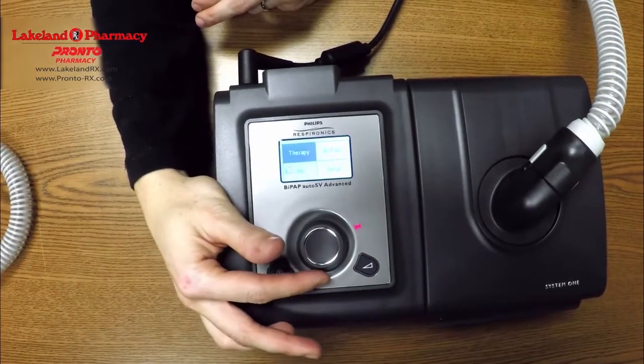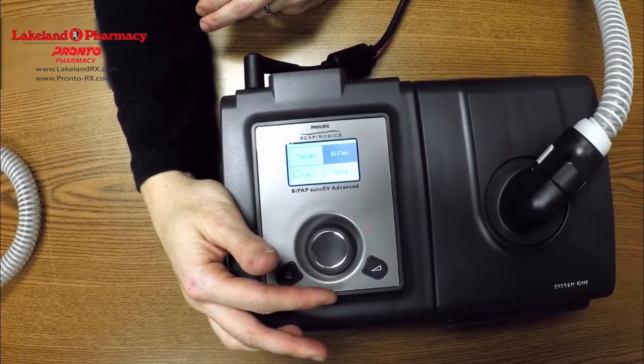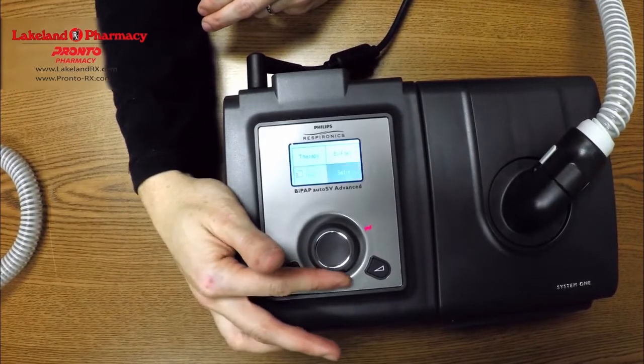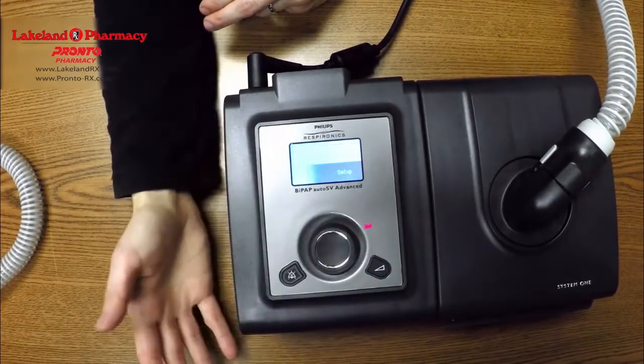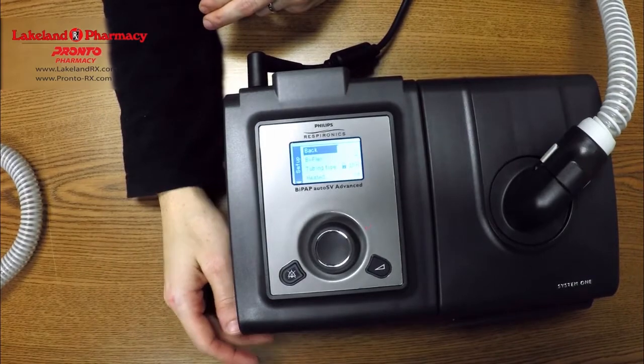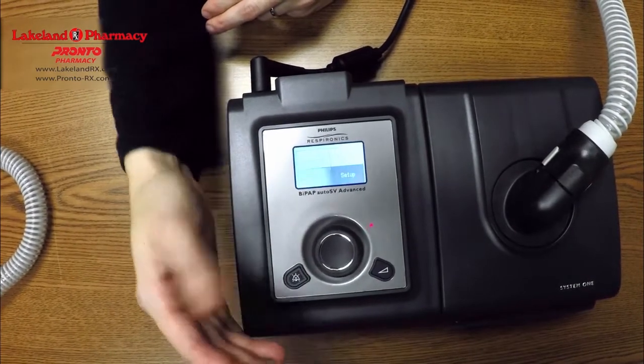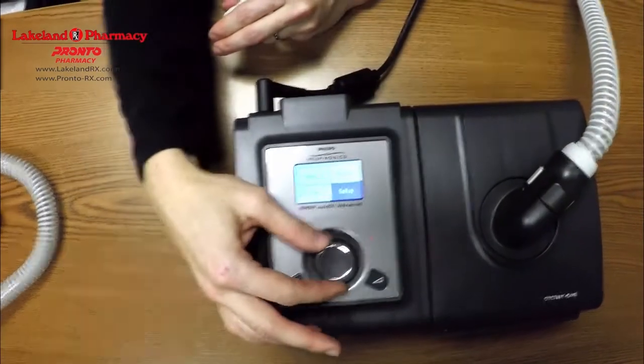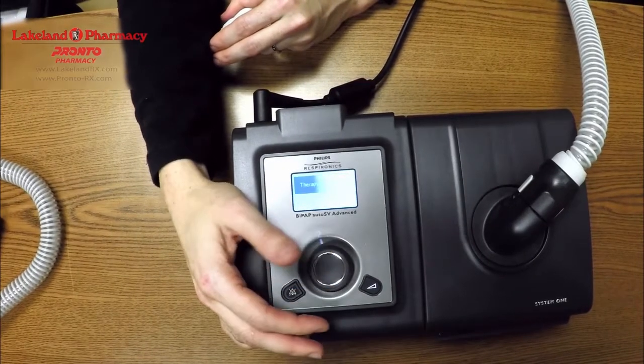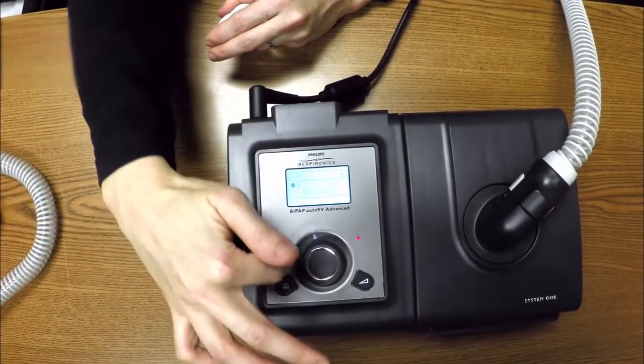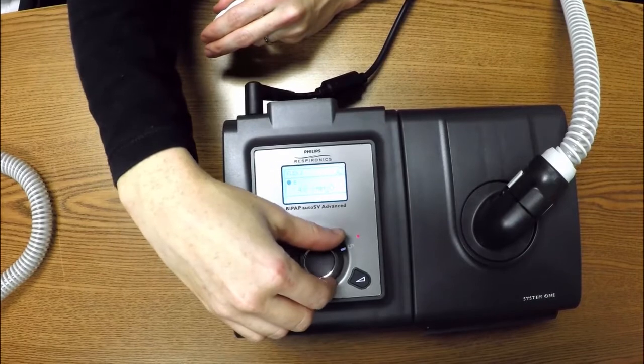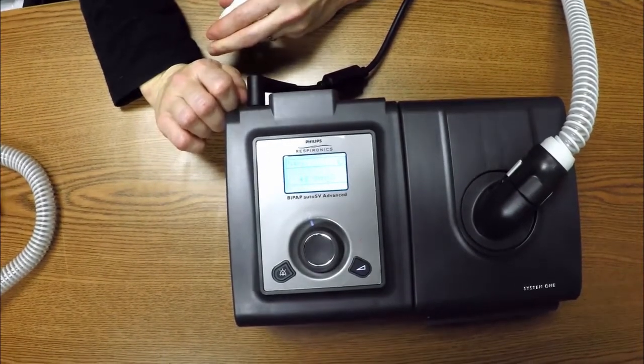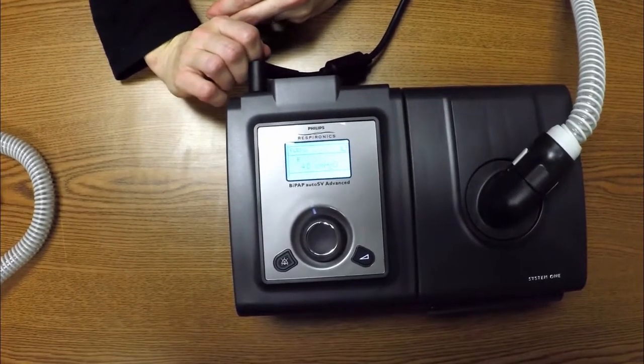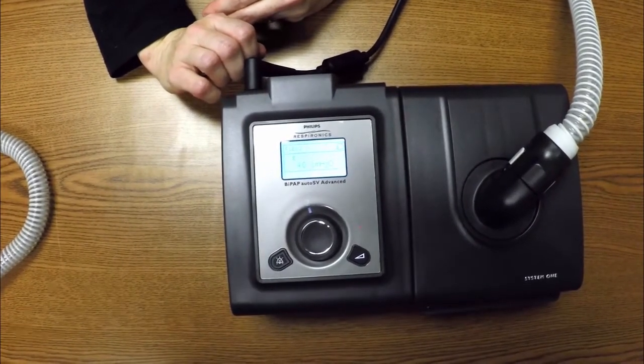Just to reiterate what we were going over: to adjust the humidity, you go into the setup menu. And to adjust the actual temperature of the tube, you go into where it says Therapy, and that will adjust your actual tube temperature. That's basically all there is to adjusting the tube temperature and humidity on a CPAP or BiPAP machine.